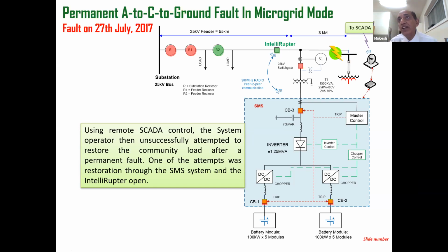An hour later, the operator thought, let me take a chance. Maybe a small tree touched the conductor, the tree is clear, the wind has gone. Let me make an attempt. The operator made a manual attempt to form a microgrid. He tried to do a black start. It was a permanent fault, and we captured the fault record by this relay.